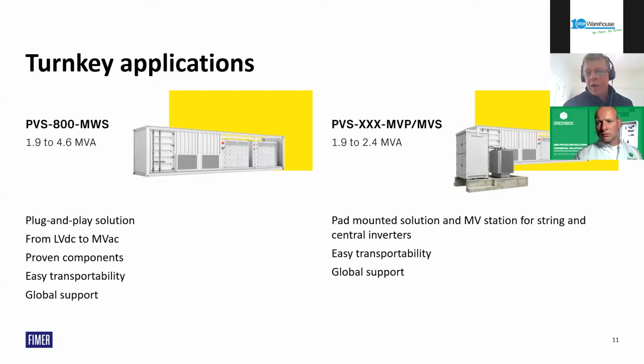For full turnkey utility applications, we've got the PVS 800 MWS up to 5 megawatts, as well as the MVS skid. You can connect central inverters and string inverters to this, the PVS 175 or the PVS 120, no worries at all. We offer a skid solution with all the MV switchgear, protection, transformer, and even an LV cubicle for string inverters to connect directly to it. So we can offer a full containerized solution for any size utility project.